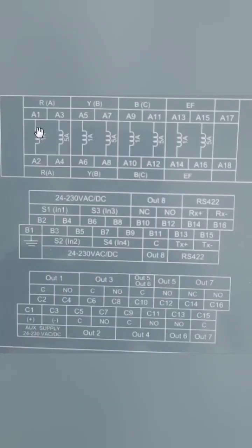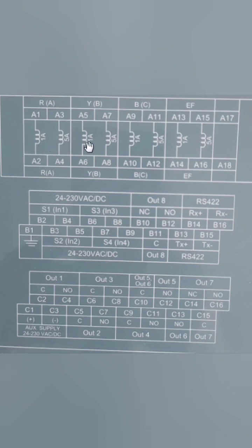We can connect protection wires either to 1 ampere or 5 ampere circuit. Our secondary is 1 ampere hence we will connect to A1, A5, A9 and A13.